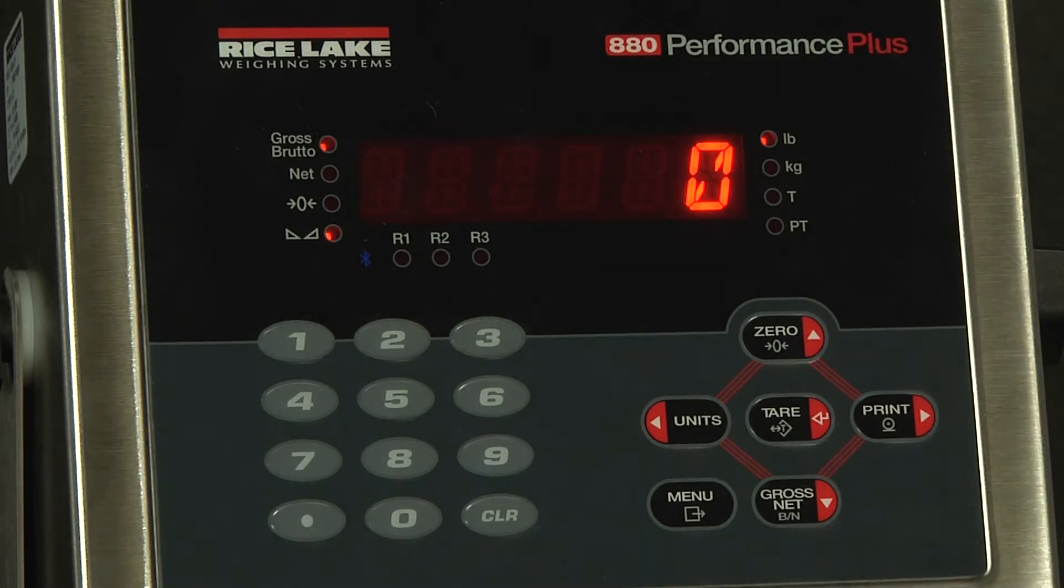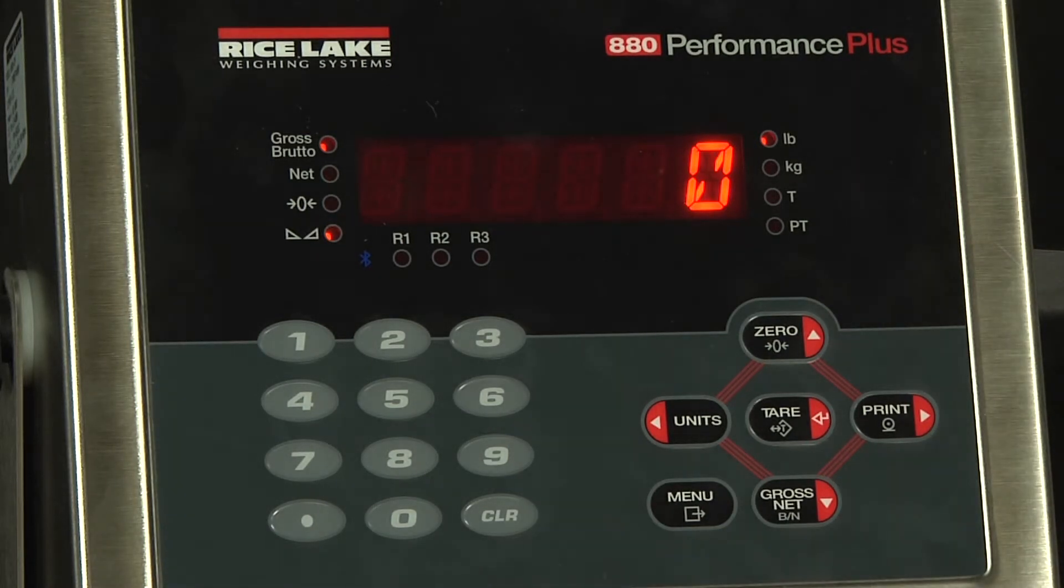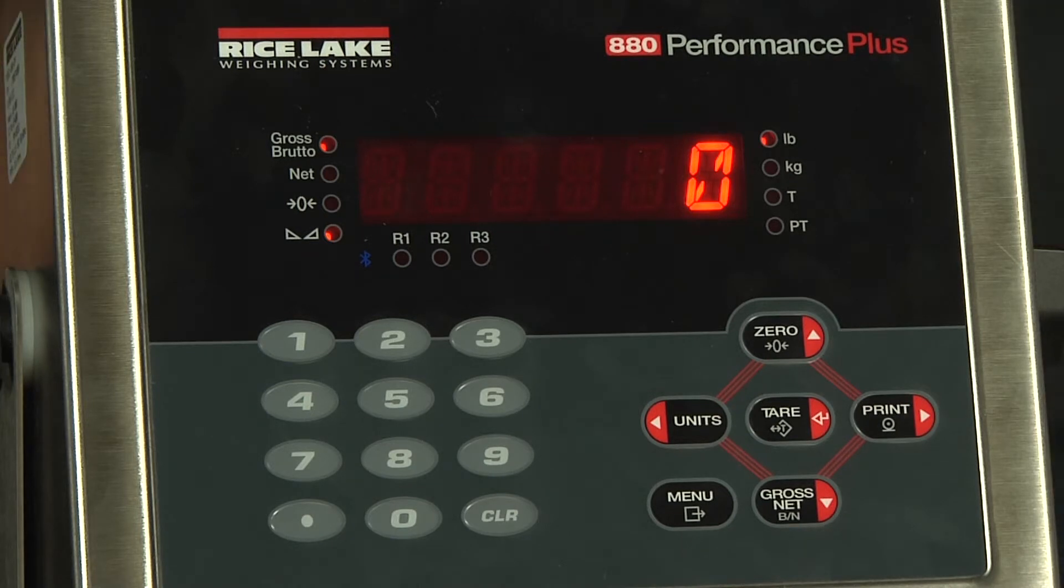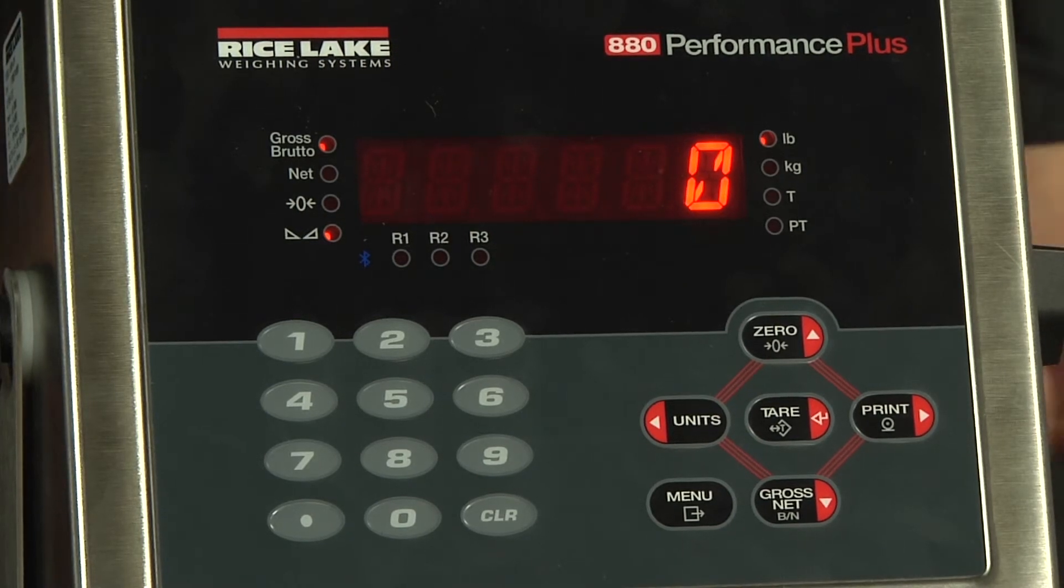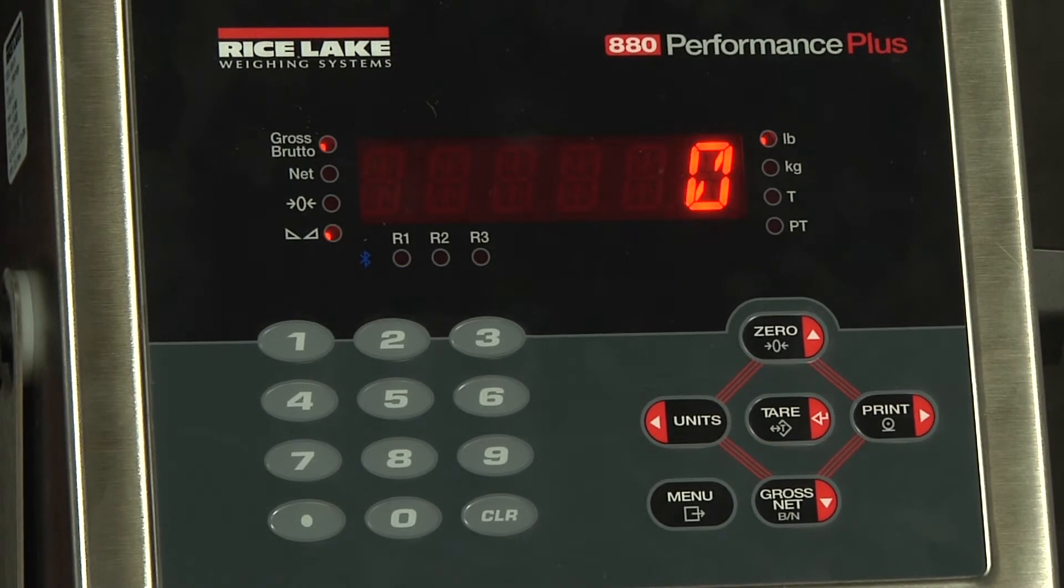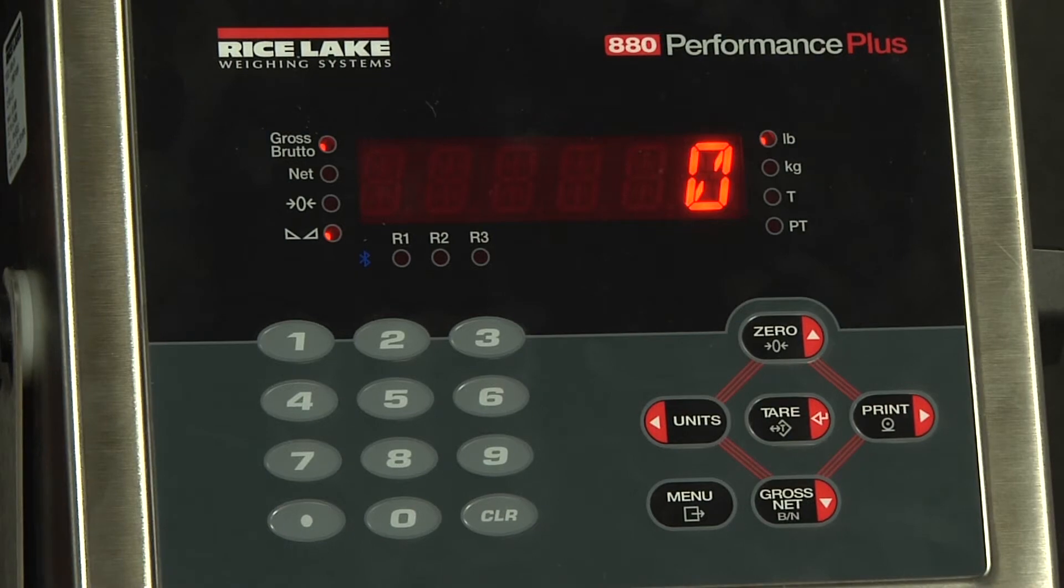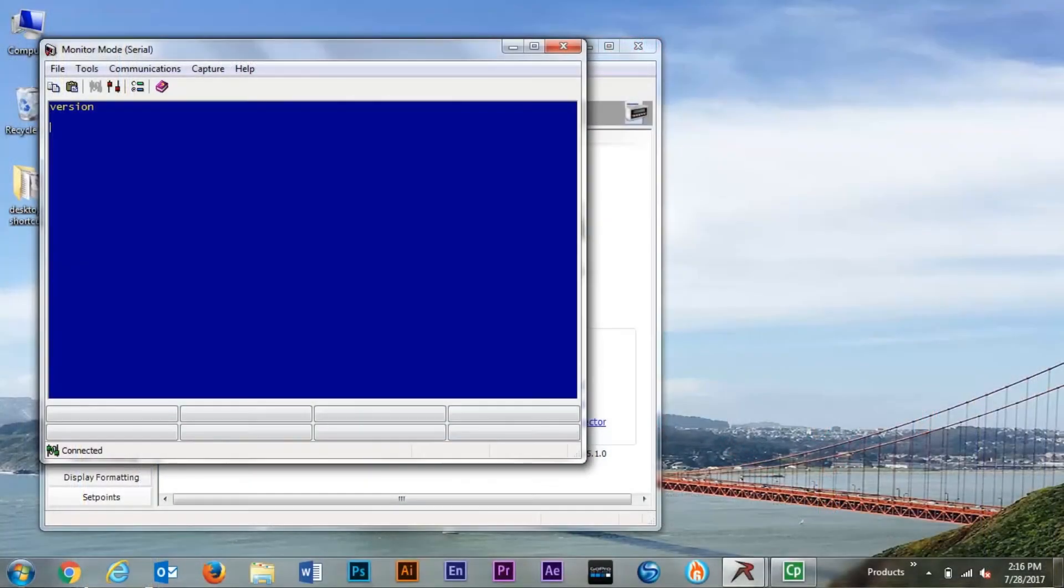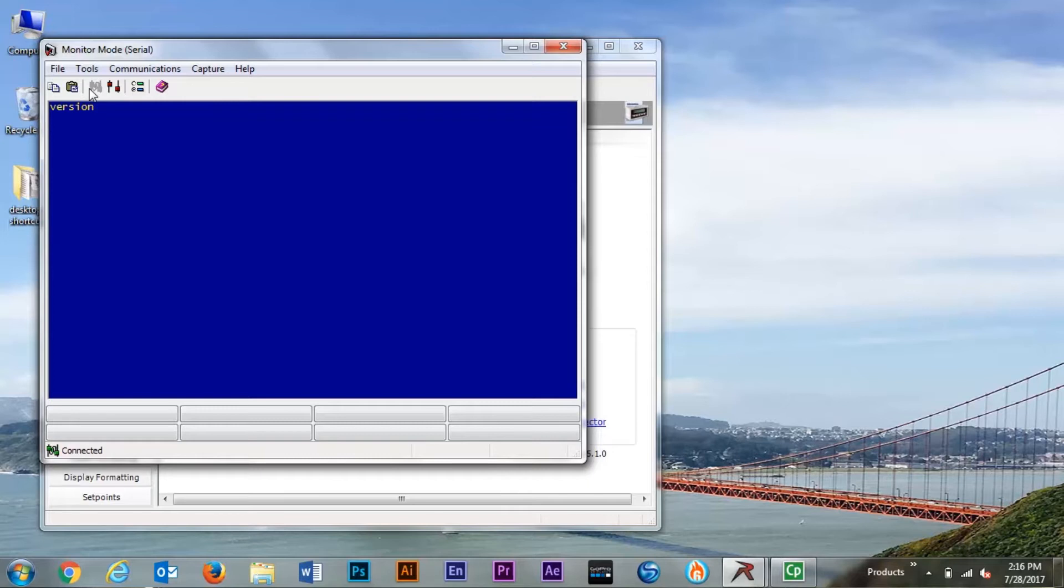At this point I will swap two wires, pins two and three on a nine pin, which are receive and transmit. Now that we've swapped the two pins, transmit and receive, we're going to hit enter, also known as a carriage return, to see if we can get a response from the 880 indicator.